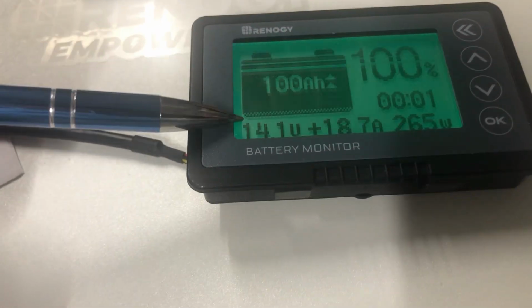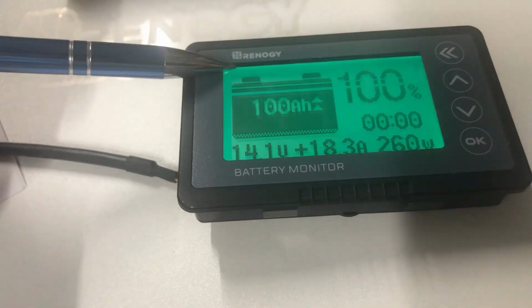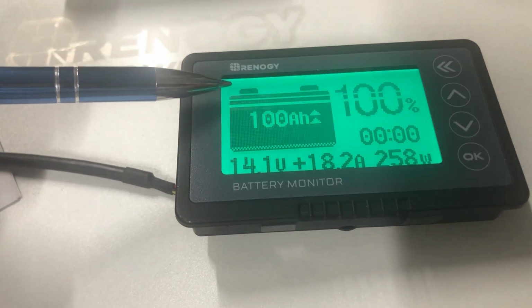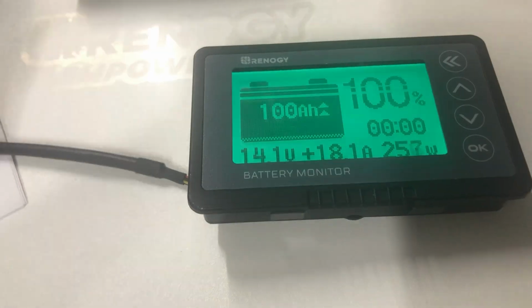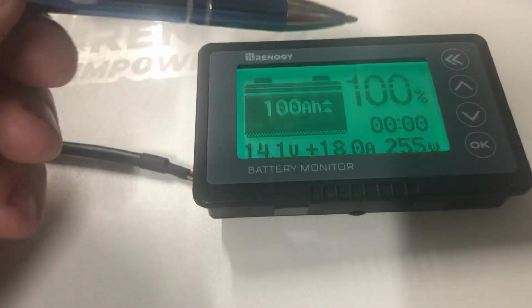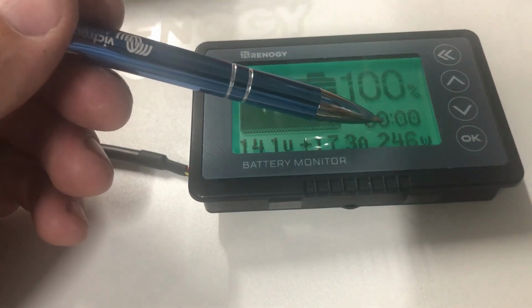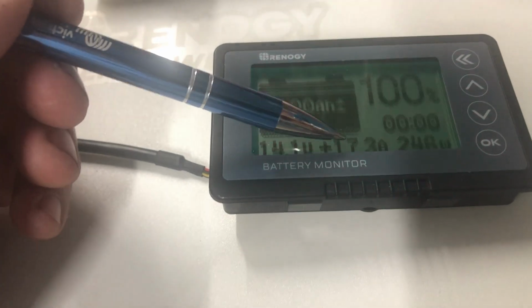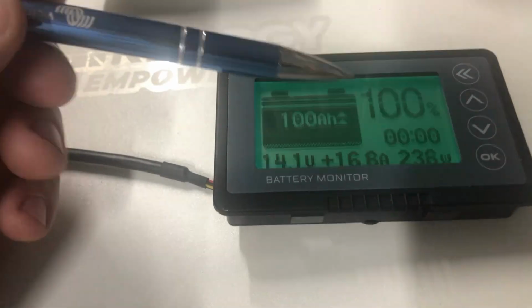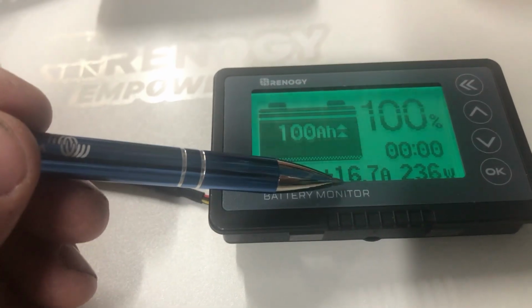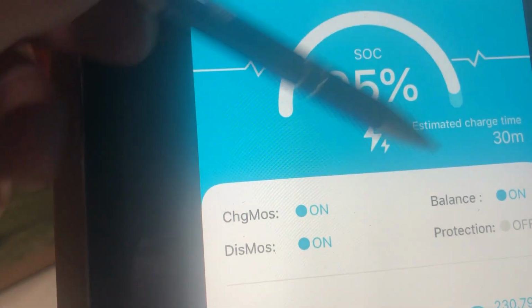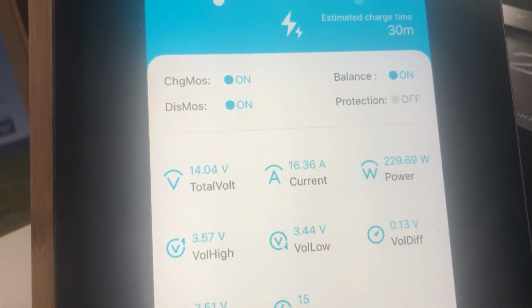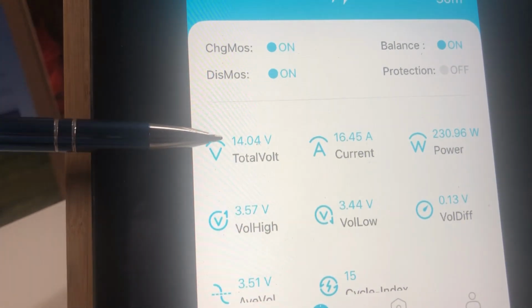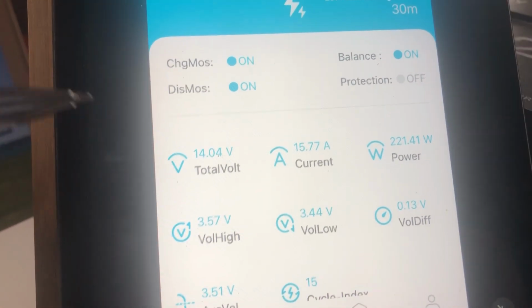As the battery was charging up, this was going up, and I assume as it comes back down, this will go back down too. We're still taking a lot of current here, which is fine, I don't have a problem with that. We're taking 17 amps, but it has cut down and you'll see that continue to drop. If we measure that against here, you'll see we're at 95% state of charge and 14.04 volts. This battery will technically be fully charged at 14.2 volts.